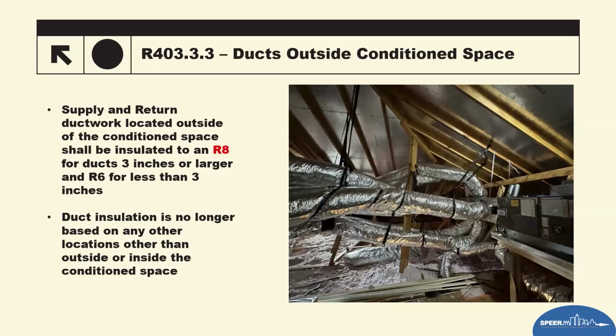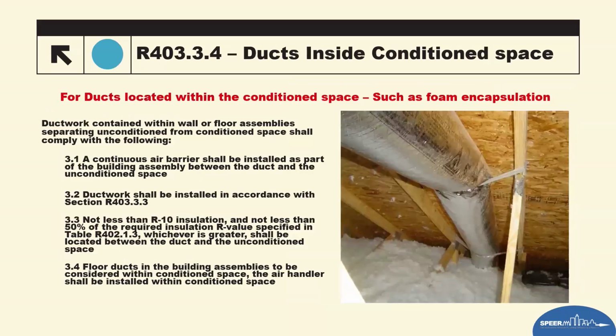And then, of course, ducts inside the conditioned space technically do not have a code requirement for insulation, but if you talk to most experts, they're going to recommend that you insulate them to at least an R6. You will not find that in the code book, but that does limit the chances of condensation on ducts if you have them insulated inside a conditioned space, such as a foamed attic.